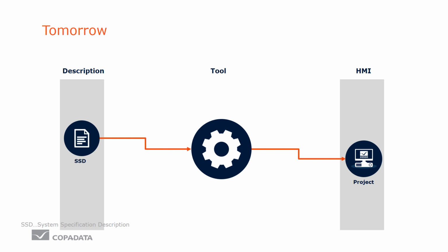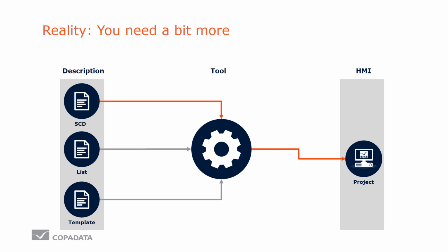But actually, there is some data missing. We understood that the SSD is missing some very important data, for instance, data that is only available in the so-called IED section and not in the substation section. But still then, we need some more information because variable names, for instance, shall not be the object reference of IEC 61850. And also usability of the HMI project is different. Some like it in this way, some like it the other way. That's the reason why we need something we call a template project.